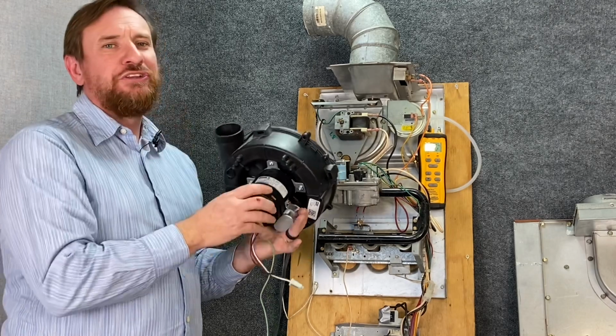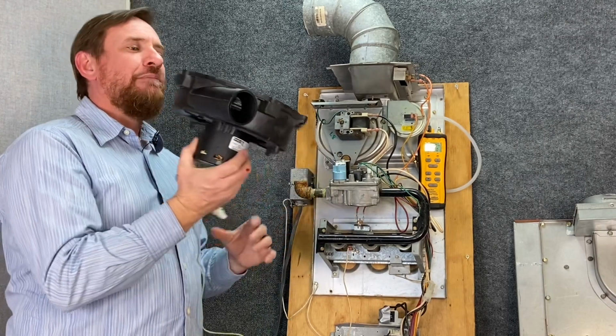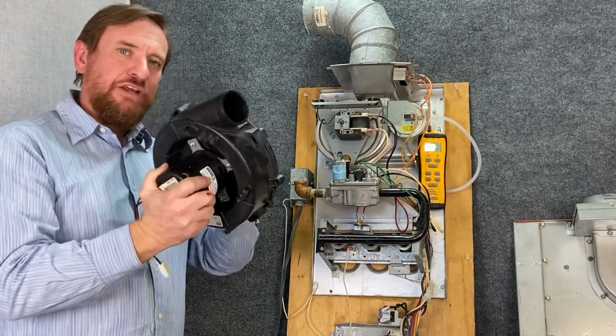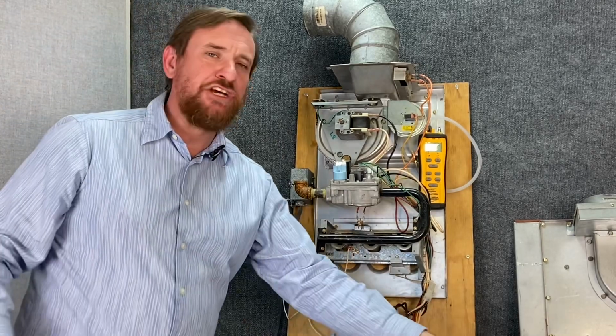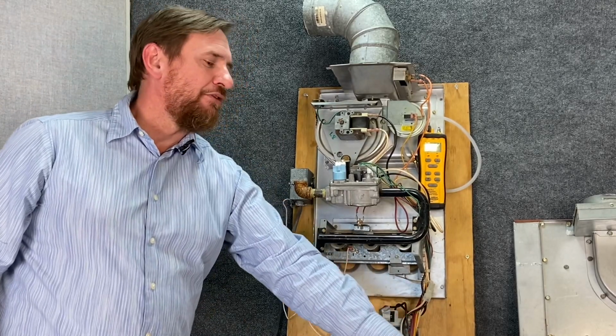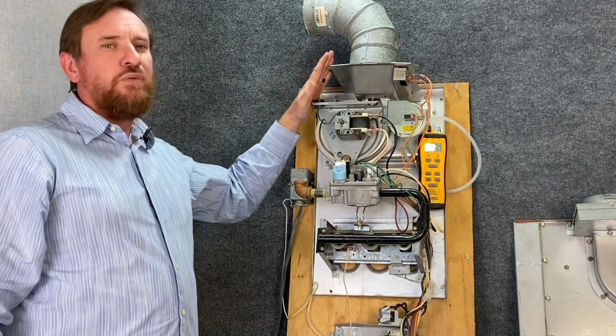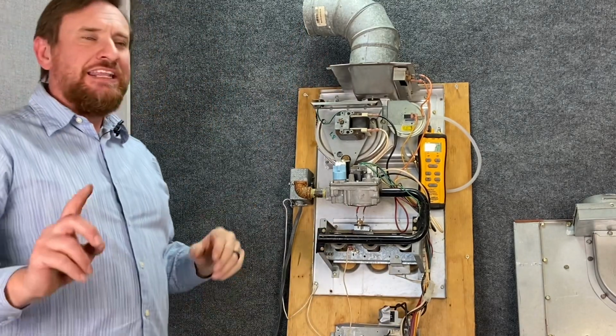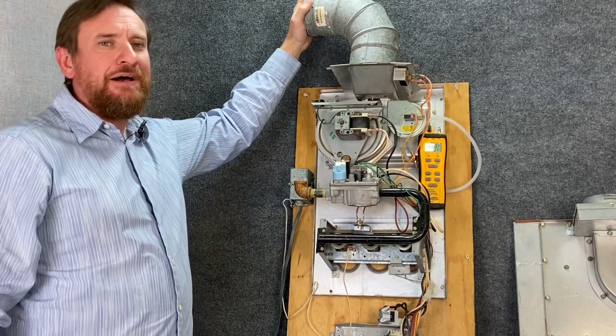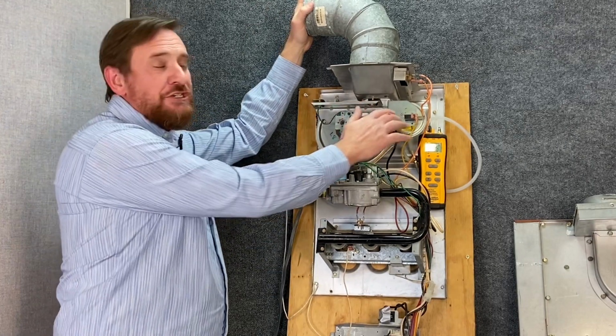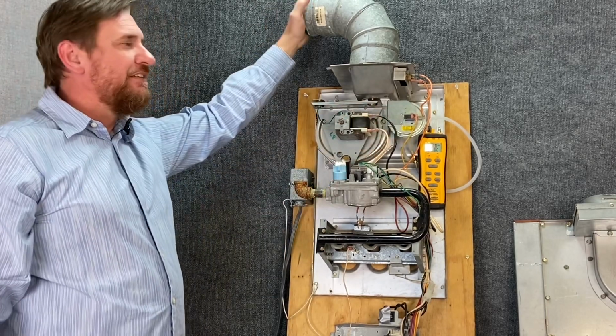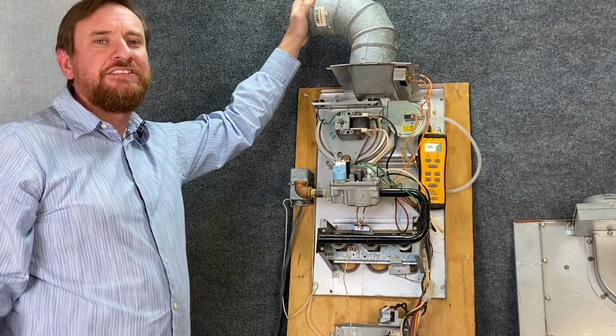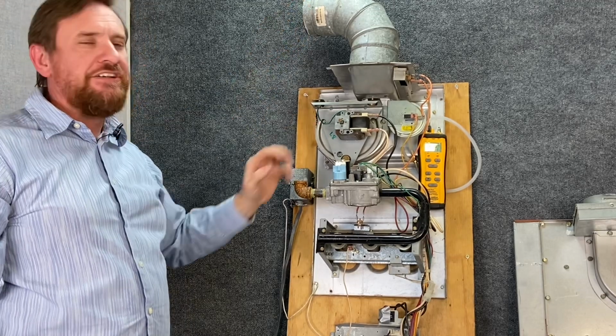Those get into a whole other aspect of checks and maintenance. But this is our inducer motor, Category 4, plastic, positive pressure, condensing, and our other most common that we see is Category 1, negative pressure. Now on that, if we have this vent pipe stopped up, it doesn't mean that we're going to have an issue with our pressure switch. We could have this entirely stopped up, leaking carbon monoxide gases in the house, and the furnace still be working.